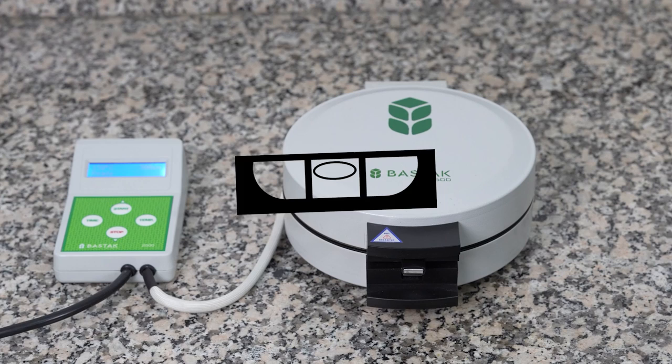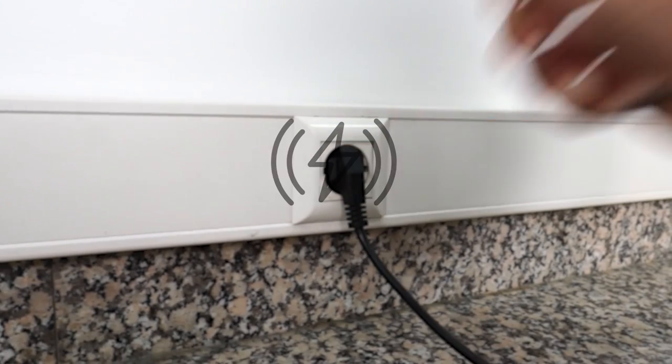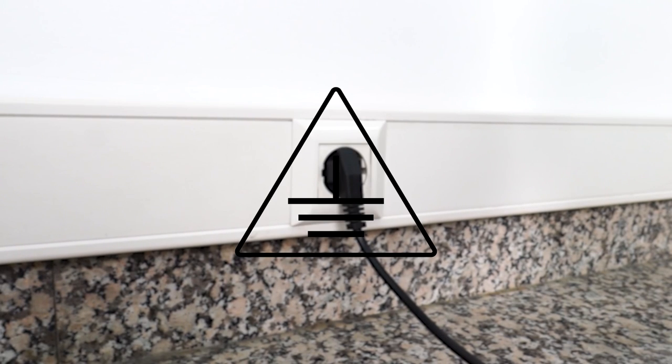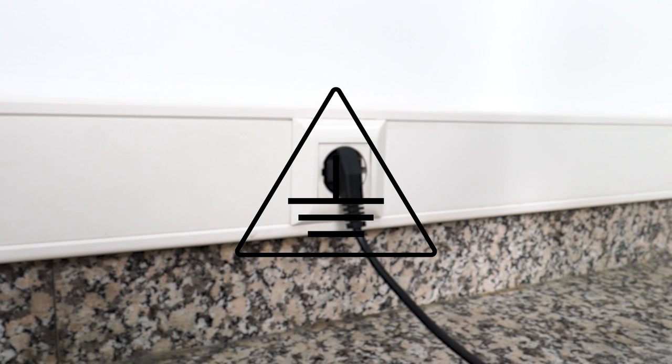The Bastak Brand 2500 model dry gluten device is placed on a flat and solid surface. The grounding of the laboratory where the device will be installed is measured. The grounding value should be less than or equal to 5 ohms. If not, the grounding line is drawn again.